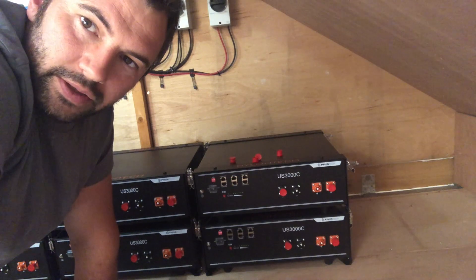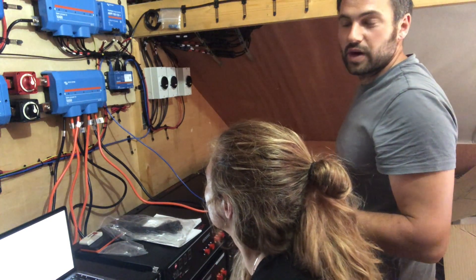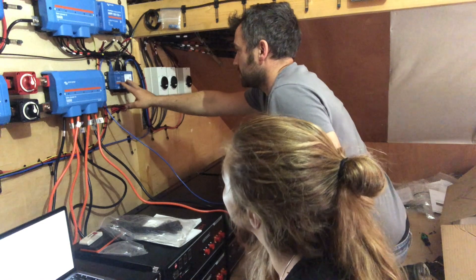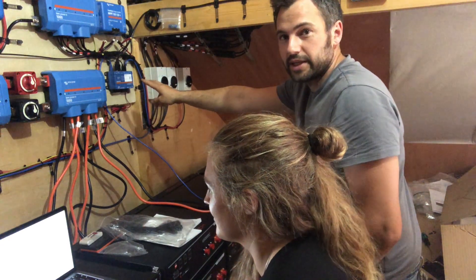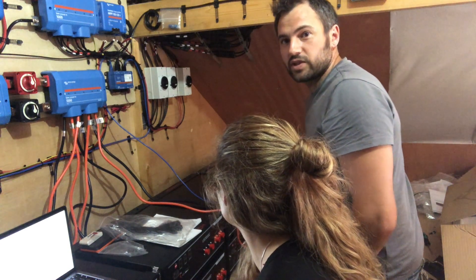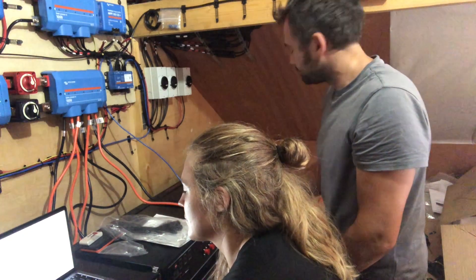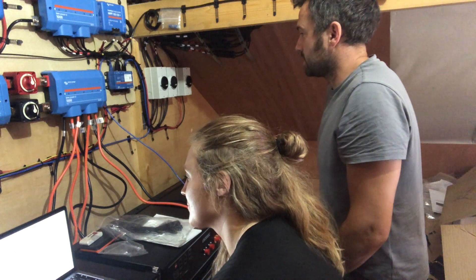We're switching on a good battery because we've never done this before, and we're going to use our MK3 device — which is for putting firmware onto things and setting up — to get the GX device working so we can see what's going on. The GX device is like the brain of the system. If we can see how a good battery looks when it's working, we might have some idea of what's wrong when we plug it into the faulty one. The voltage on the faulty one was slightly less but not enough to be an issue — it should still work.